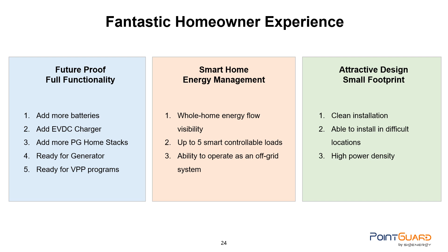This is not the time to get into all of the details of our V2X charger, the bidirectional DC EV charger. However, I would like to clarify why it is an oversized, up to 25 kilowatt charger. When charging from the grid, you can import up to 11.4 kilowatts of AC power, which is converted by our inverter into DC power. You can import up to 11.4 kilowatts because that's the maximum power output of our controller. In addition, whatever the PV can contribute is additive to the charging power.